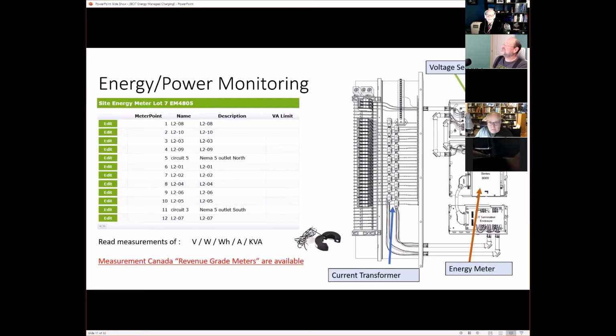Now, it's important to understand that these energy meters installed in this manner can be revenue grade meters approved by Measurement Canada. You buy the right current transformers and the right meters, and then you get them certified and sealed to ensure that they're accurate when they were sealed. And you would now be able to bill by the kilowatt hour using these measurements because Measurement Canada has approved the metering.